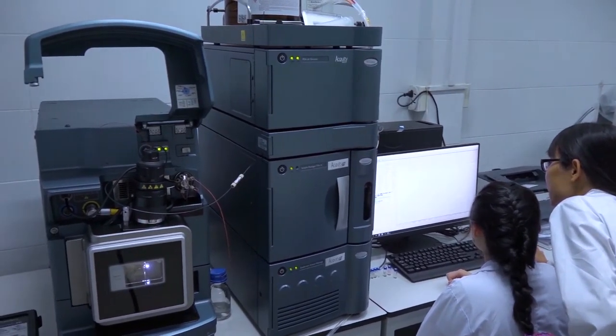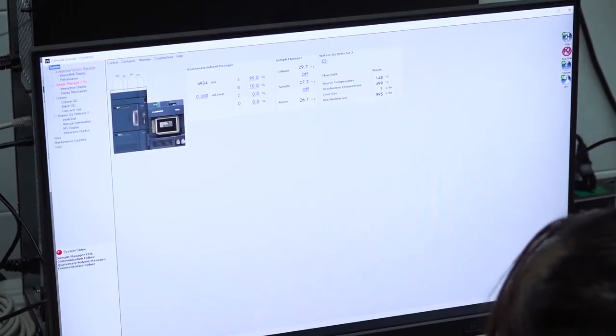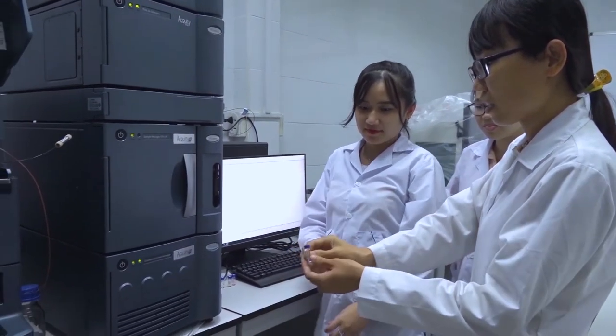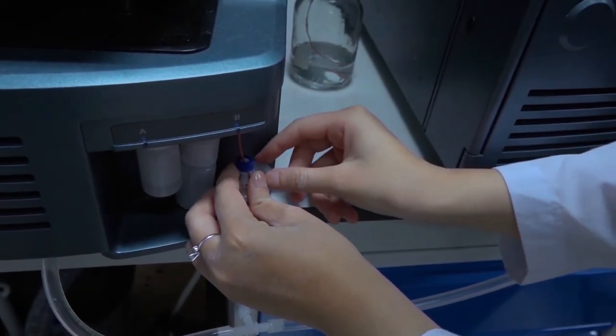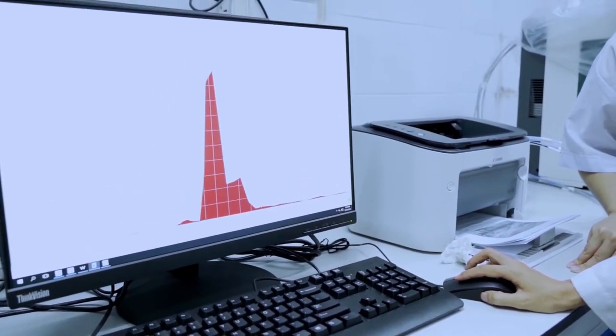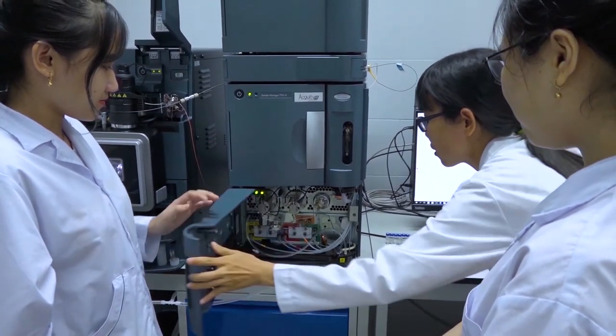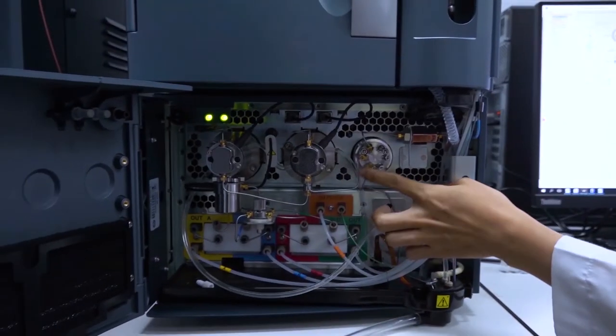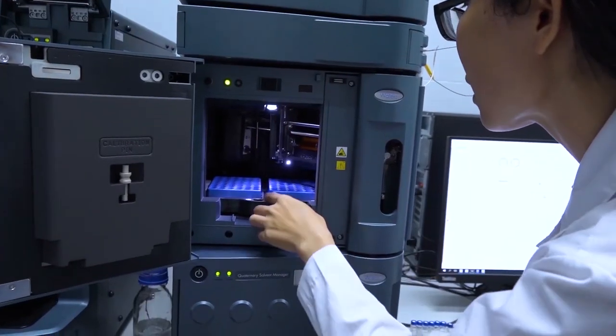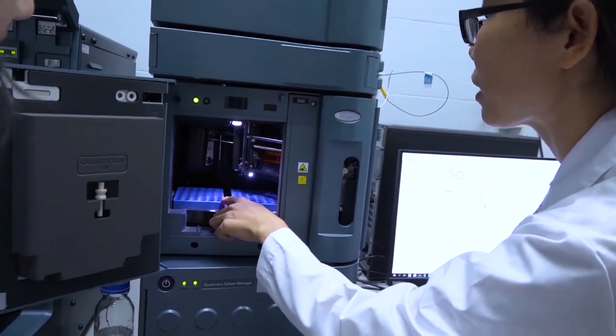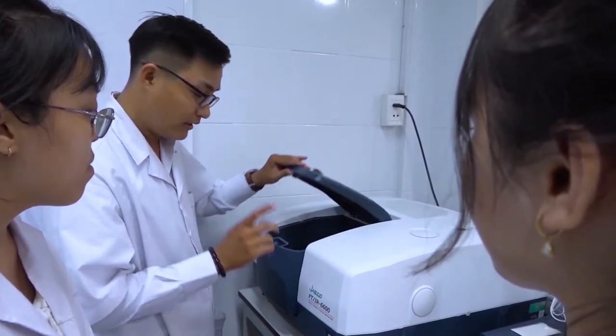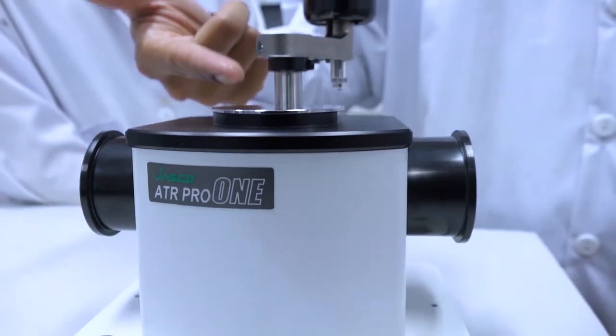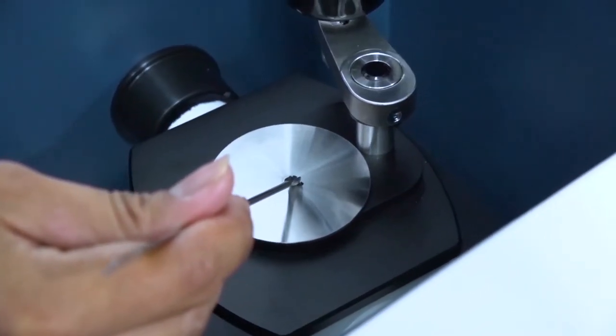Ultra-performance liquid chromatography coupled to photodiode array detector and mass spectrometry detector is a specifically analytical instrument used to separate, identify, and quantify each component in the mixture, especially organic compounds based on the difference in physical chemical properties of these compounds. The UPLC-PDA-MS is not only a specific technique for basic research, but also in cosmetics and pharmaceuticals.